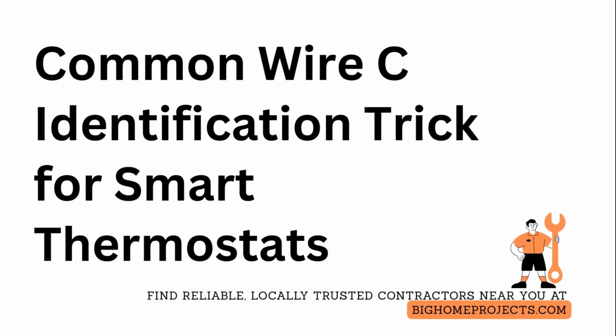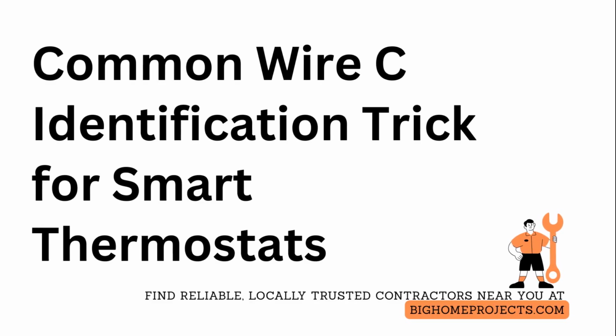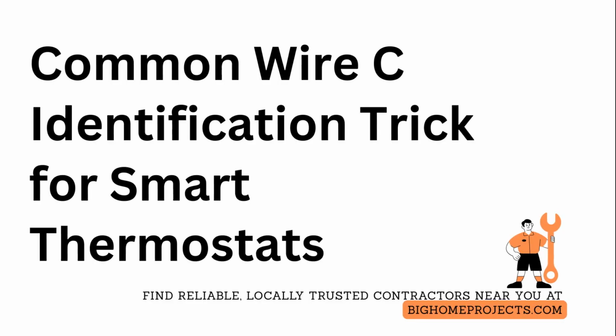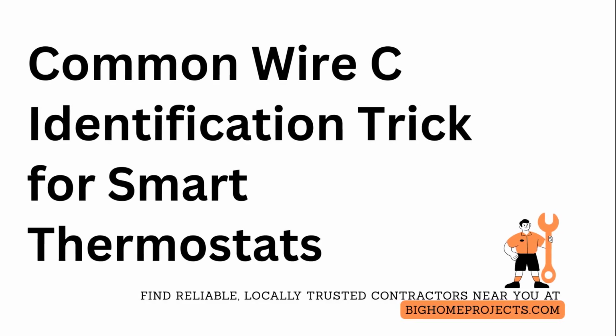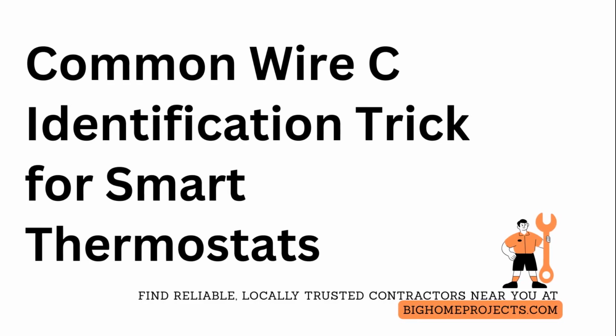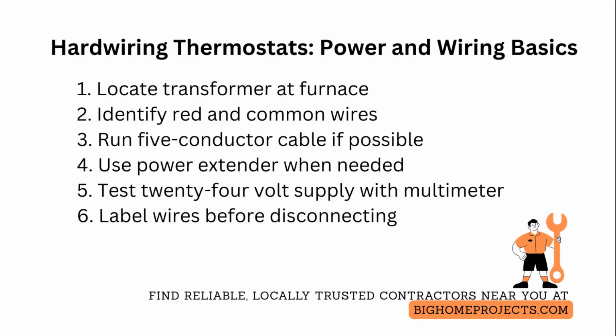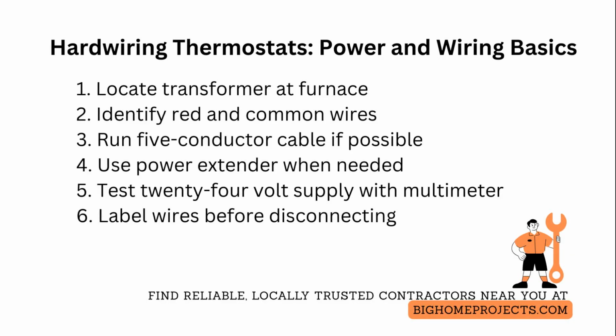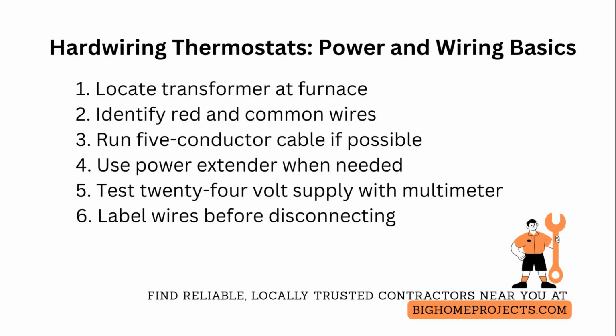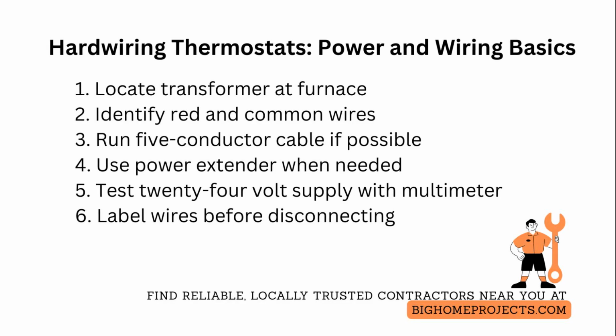Hardwiring a thermostat means wiring it to the furnace or air handler's 24-volt common and power wires, so the thermostat has continuous direct power instead of relying on batteries. Hardwiring a thermostat requires locating the transformer bundle at the furnace or air handler, identifying the red wire for 24-volt power and the common wire for continuous return, and running a 5-conductor cable from that control board to the thermostat location so each function has its dedicated conductor.